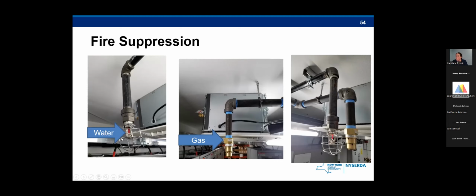So these suppression systems should not be open head sprinkler or spray nozzles, and the water should only be placed on these systems when there's a known fire event. So basically for this water sprinkler system, if it gets too hot, this glass thing basically breaks, and then they're able to supply water to the system. And then they also have clean agent or gas systems set up next to it as well. You can kind of notice the difference between the two nozzle assemblies. So depending on what is happening inside the container, they have two different fire suppression methodologies that they can utilize.